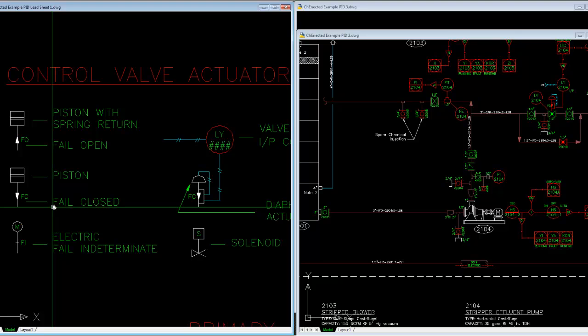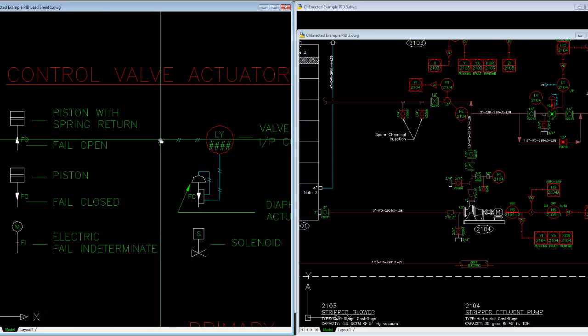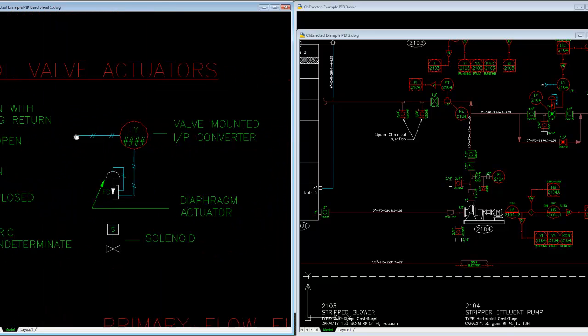That and fail indeterminate are loosely connected with the exception that I think in the fail indeterminate, you simply have no idea where that valve's at in the field. There's no feedback from that valve on its position, and it's unknown where it's at, which is clearly not a good condition to be in.